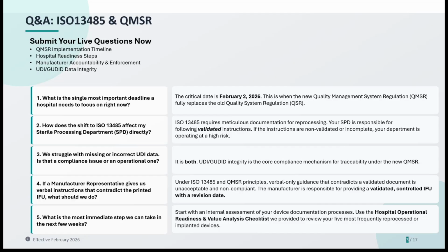Number one, what is the single most important deadline that manufacturers and hospitals need to focus on right now? The critical date is February 2nd, 2026. This is when the new QMSR fully replaces the old quality system regulation. As of this date, manufacturers must adhere to the principles of ISO 13485:2016. While this is a manufacturer deadline, it empowers your hospital. If their documentation is non-compliant, you have the regulatory backing to reject or suspend the use of that device at your facility.